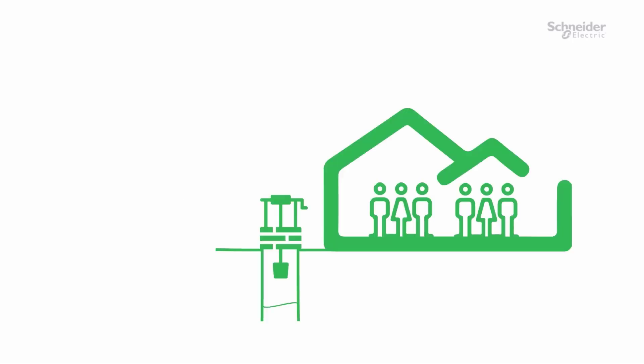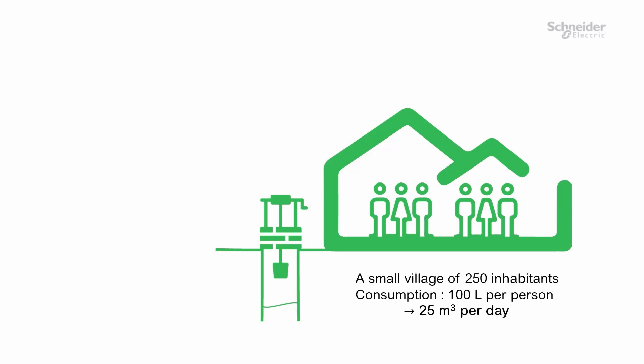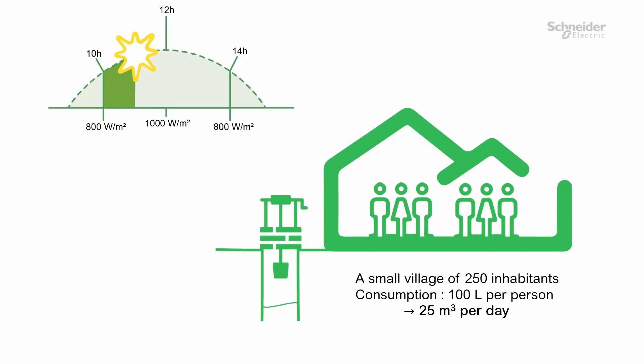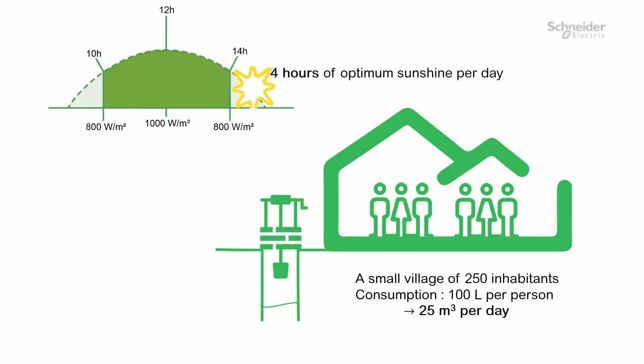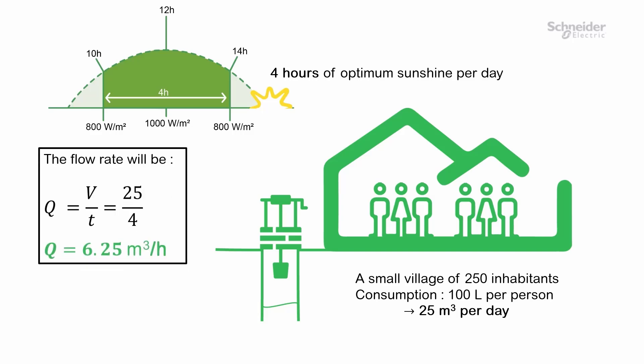In this video, we will take the following use case as an example. In a small village of 250 residents, the water consumption is estimated at 100 liters per person, totaling 25 cubic meters per day. Sunshine conditions are unfavorable with only 4 hours of optimum sunshine per day. Given these parameters, the required flow rate is 6.25 cubic meters per hour.